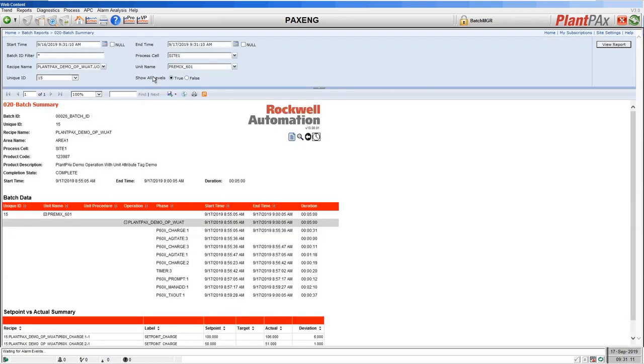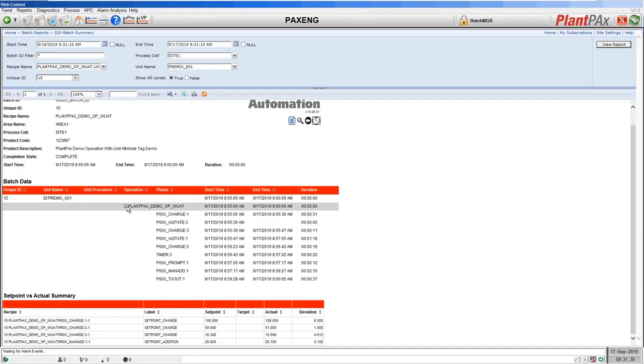The next report is the batch summary, which gives you a summary of the report. Here you can see at the top the details of the batch ID, the unique ID the system gave, the name of the recipe, where the recipe was run, its final status — in this case complete — when it started and finished, and how long it took. You can then see for each of those equipment phases — the processing steps — when they started and stopped, and how long they took. At the bottom you can see the setpoint and actual summary. For each of those equipment phases where they were given a setpoint and they report actual amounts — such as the charge phase in our example — you can see the amounts specified by the recipe, the actual amounts reported back, and the deviations. Very useful to see if a batch is within your acceptable tolerances.